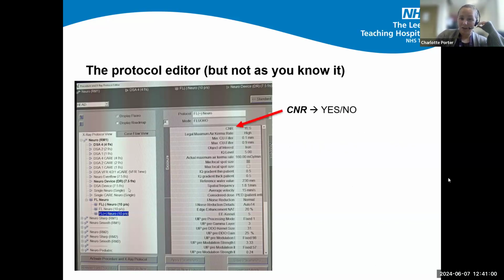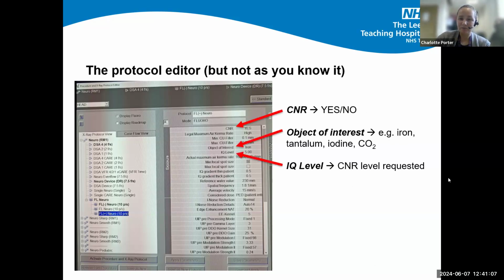One of the first things on here is this CNR box. It's a yes or a no. If it's yes, then it's going to be a protocol that uses contrast and noise regulation. There are these two elements here. So the object of interest: you have to specify for a particular protocol what the object of interest is. So it could be iron, tantalum, iodine, CO2. It will depend on what the clinical task is that's being achieved with that protocol. And then the image quality level is set. That is essentially the CNR level that the protocol is requesting that the system aims to achieve.